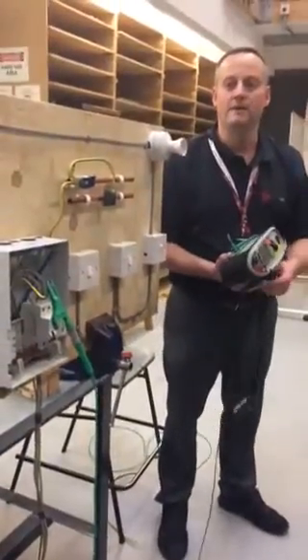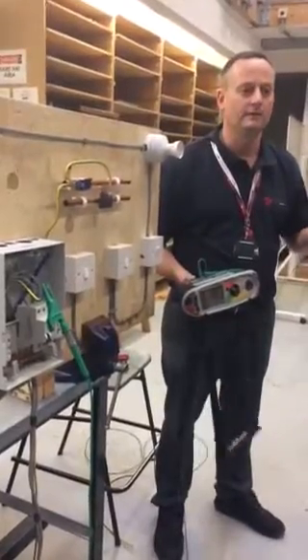So the distribution board needs to be off before the test is carried out. We're using a long 50 metre lead this time, as we would in an installation, and we've removed the resistance of it earlier as stated in a previous video clip on how to remove the resistance of leads.